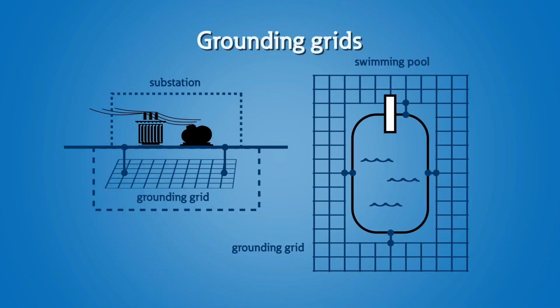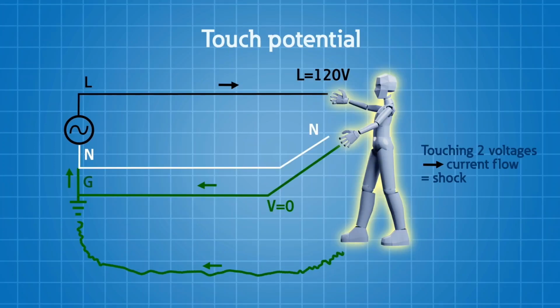So we expand this concept. If you think about the concept of touch potentials or step potentials and keeping things at the same potential, you can think about this in regard to substations, where we establish that grounding grid underneath the substation, or around swimming pools where we're doing equipotential bonding. This will reduce the likelihood of voltage potentials, and we understand that a potential difference between two voltages is what's going to drive current. So if we can reduce or eliminate that potential difference, we can reduce the likelihood of shock, so we can reduce the likelihood of damage to electrical equipment.